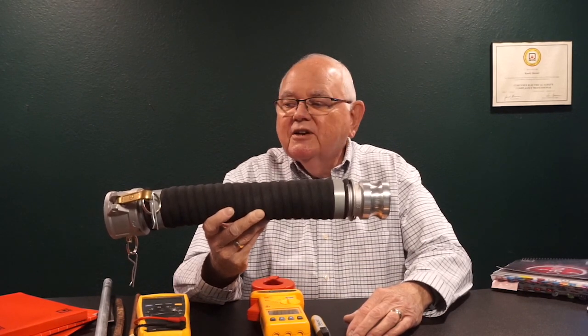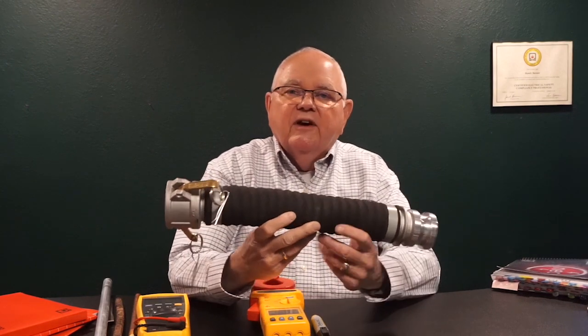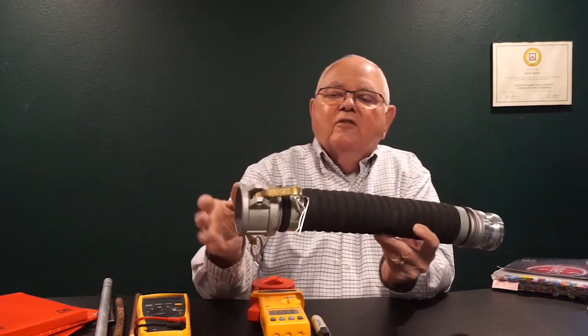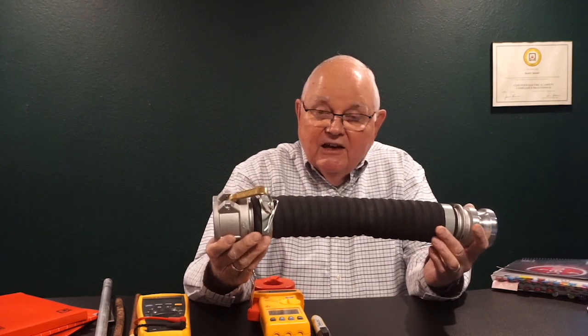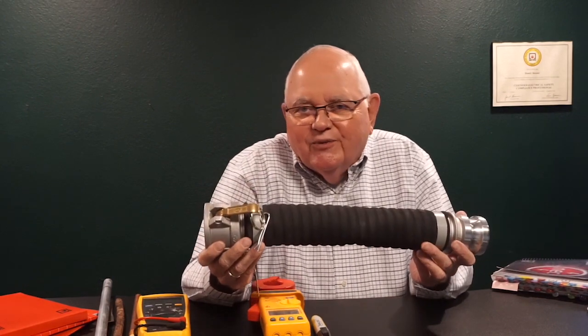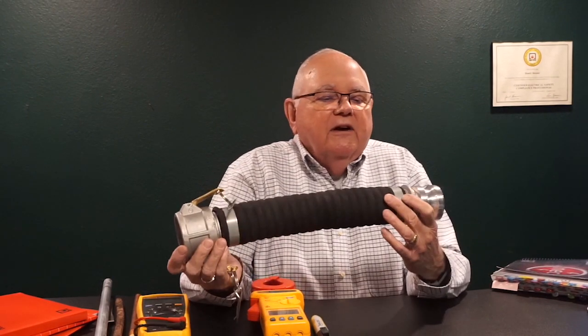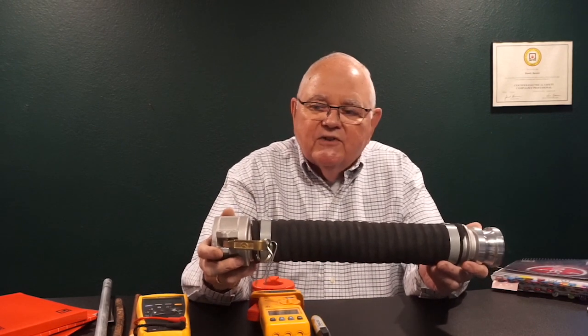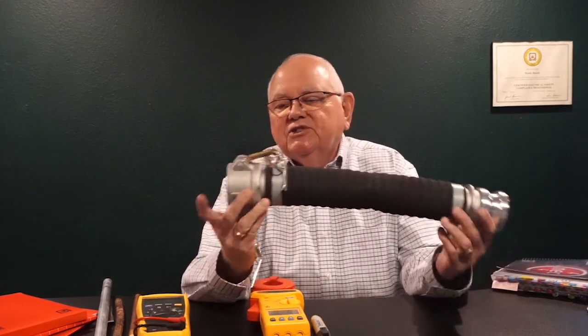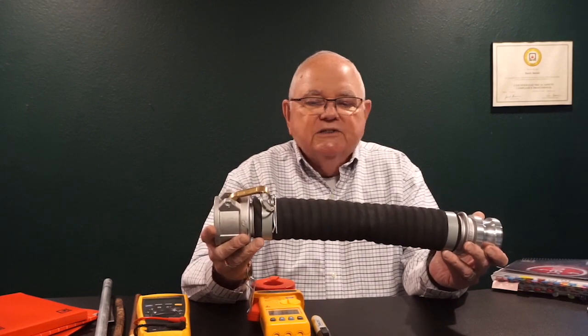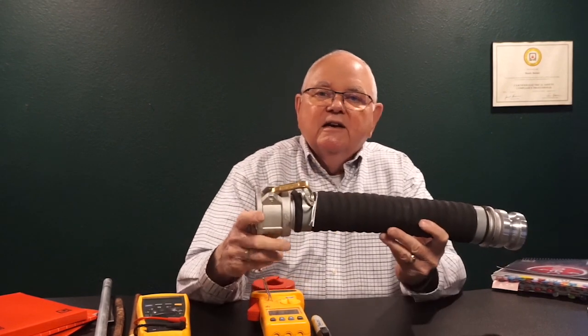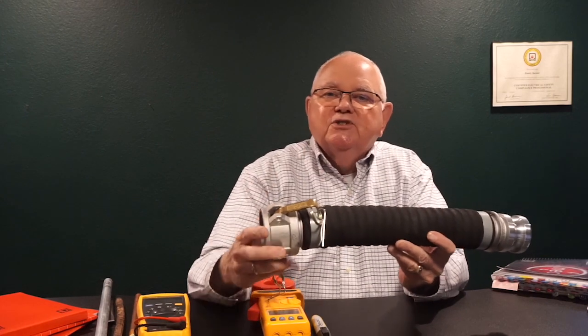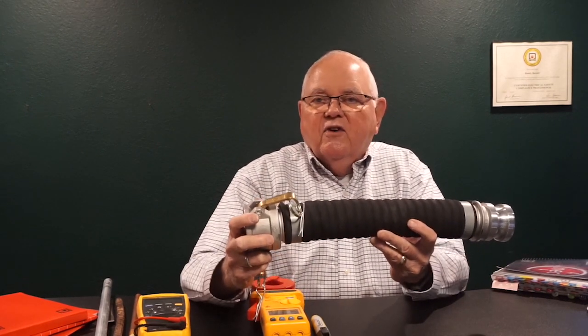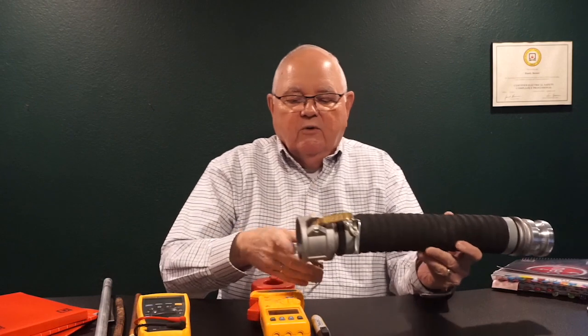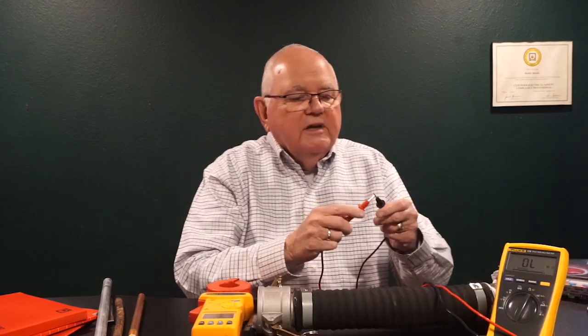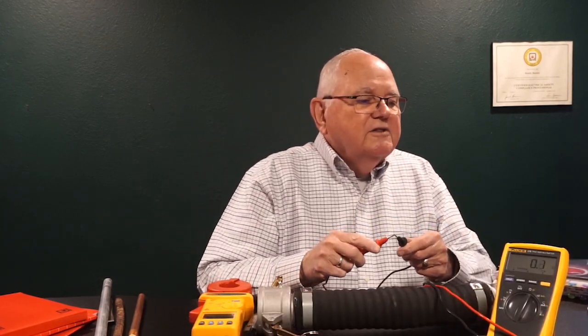So this particular hose, yes, it's different. It actually has a piece of wire that runs through the hose and connects at each end. So it's actually not the rubber that I'm using for the bonding. I set you up for that one. There is a small piece of wire that runs on the inside of the hose, connects at each end of it, and that is how I'm able to accomplish bonding, so that I keep that difference in potential the same between that tank and that truck as I'm filling up the truck or whatever it is I'm doing, or emptying the truck. Make sure our meter works on resistance.